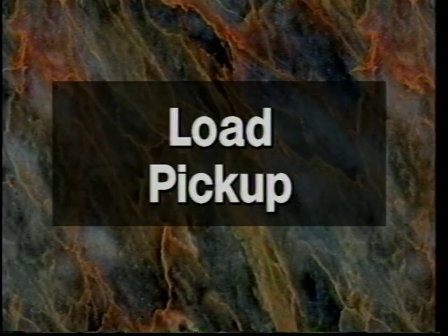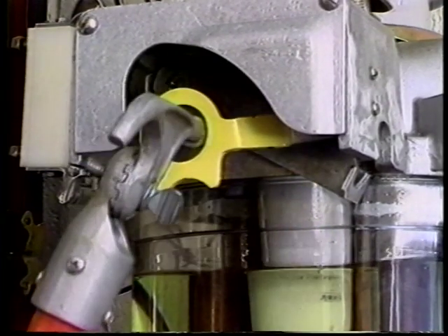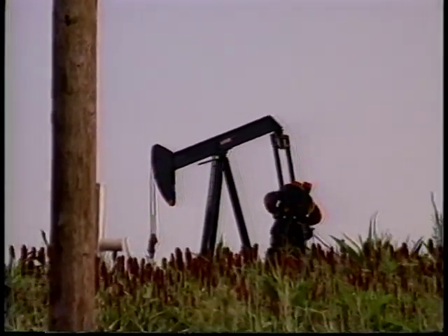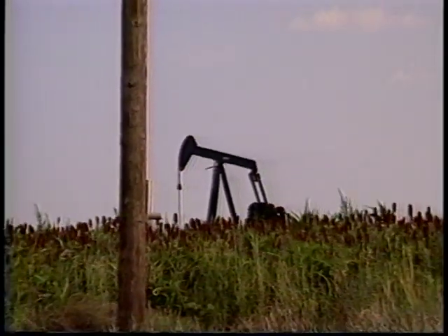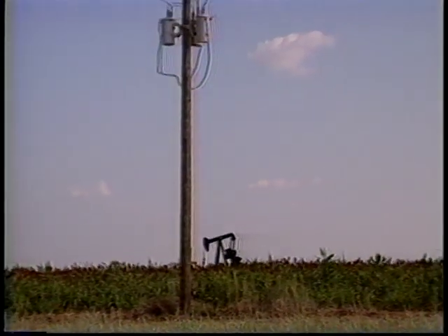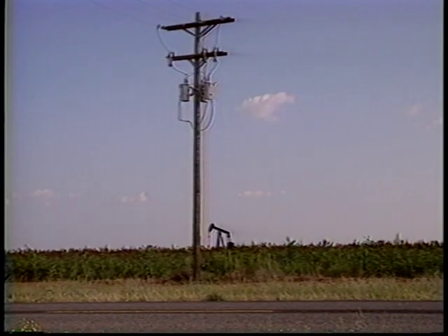Load pickup. The inrush current experienced in closing a recloser after a lockout operation may occasionally introduce some difficulties in getting the recloser to latch closed. The highest inrush current can originate from automatic starting motors, or magnetizing current of transformers. However, these types of inrush currents are normally short-lived.